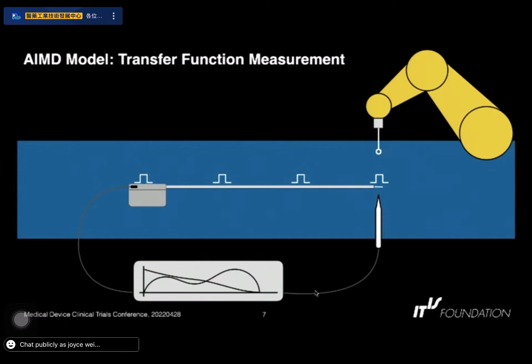So the voltage is induced at the other end of the lead in the device, and we measure the magnitude and phase of these responses as a function of the pulse that's swept along the tip, and this creates a so-called transfer function measurement. For a passive implant, instead of a transfer function measurement, because it's not a long device, we would have a more simple amplification factor. So if you put in a field applied to it, how much does it amplify those fields?